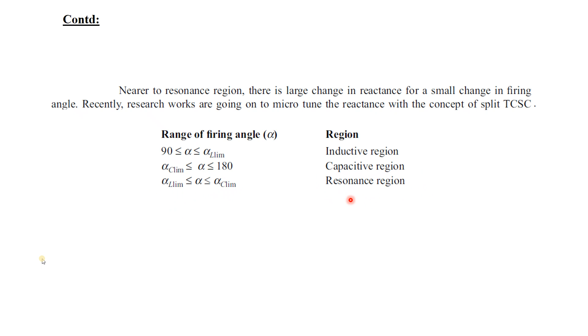Recently, research works are going on in tuning of the reactance with the concept of the split TCSC. Now the range of firing angle: if the firing angle is greater than 90 and less than the inductance limit, it is called the inductive region. If the firing angle is greater than the capacitive limit and less than or equal to 180 degrees, it is the capacitive region. And within this limit, we have the resonance region, where there is neither an inductive nor a capacitive period.